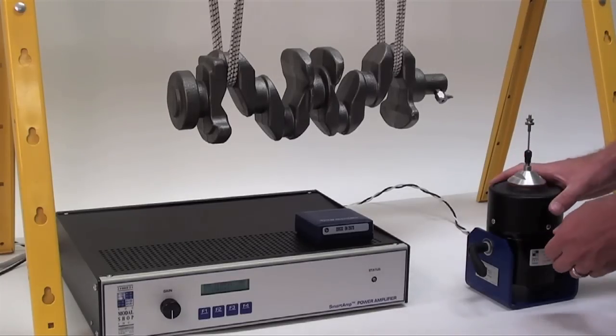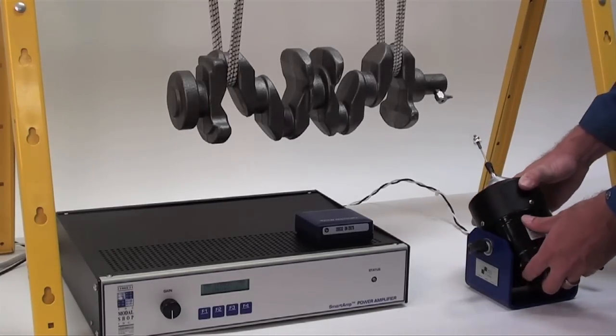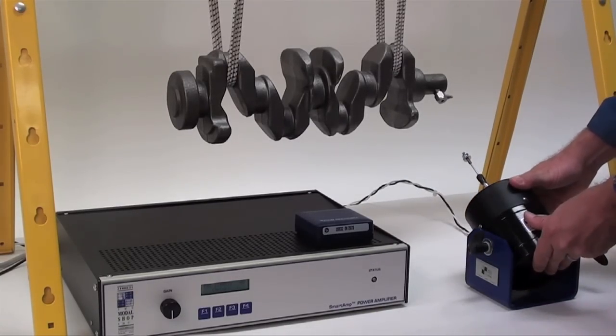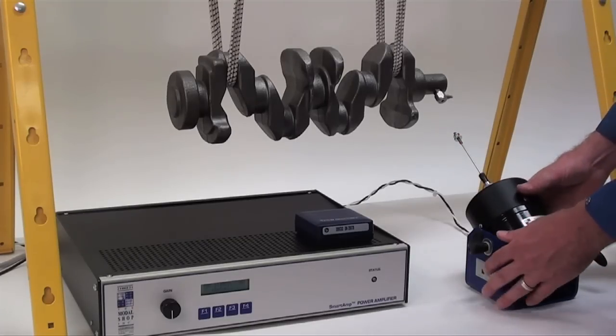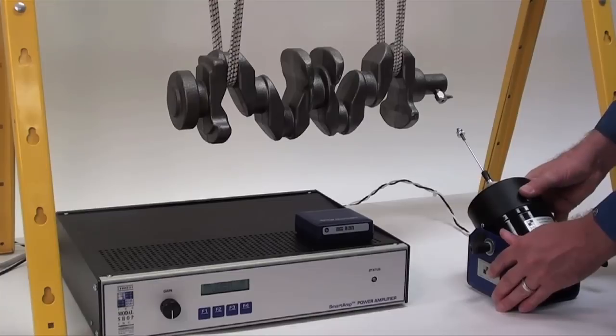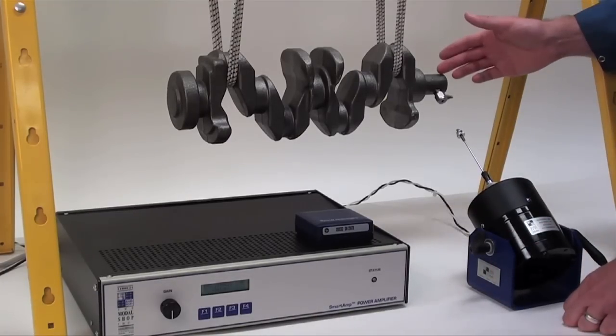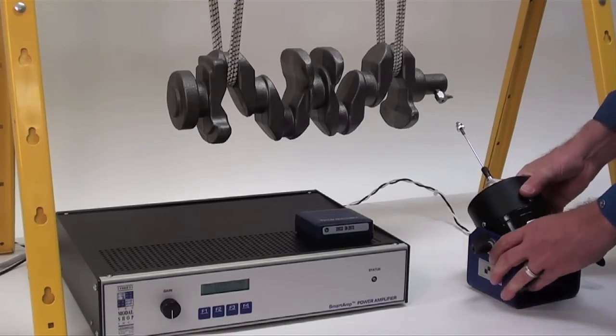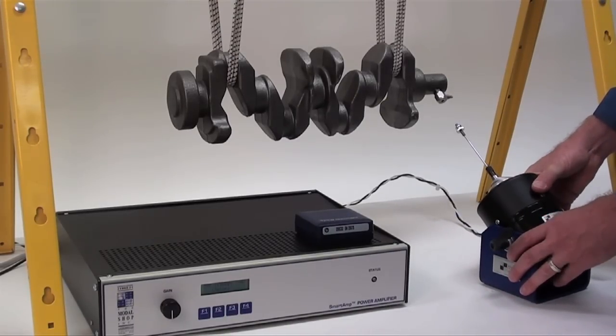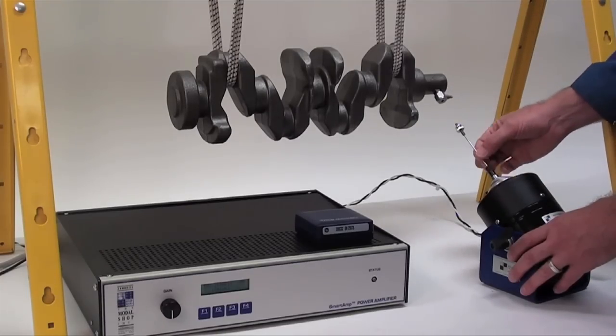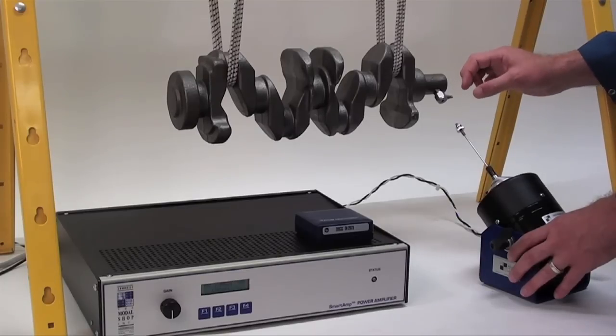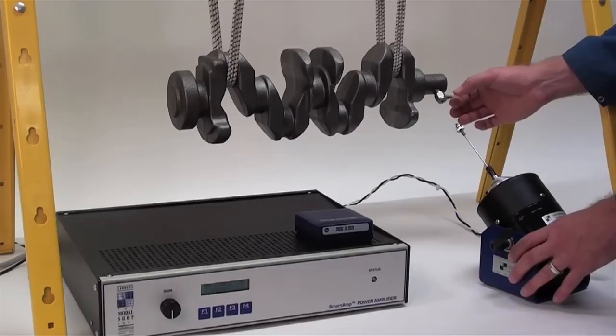And we have to be particularly careful about shaker alignment. We want the shaker and stinger to be perfectly aligned with the load cell for several reasons. One reason is we want to minimize the cross forces which are being applied to the object. If the shaker is not aligned with the load cell, we'll be putting in a force normal to, or along the line of the stinger, but we also may be imparting some side forces or moments to the structure which won't be measured by the load cell.